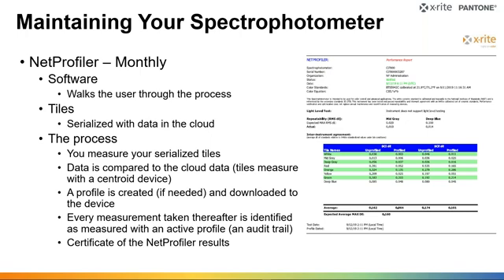And that 0.1 delta E, again, depending on what your tolerance is, can mean the difference between pass and fail, right? It can mean the difference between you going out and troubleshooting a color problem that might not have needed troubleshooting because the instrument contributed a little too much to it.